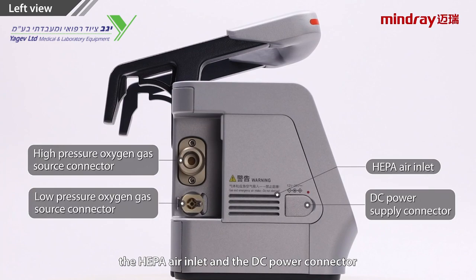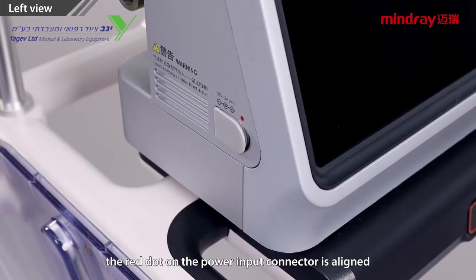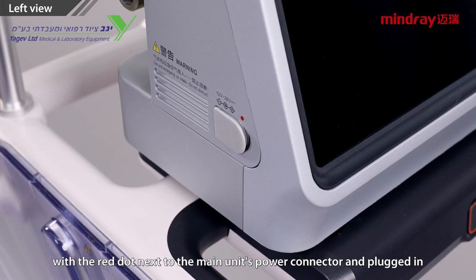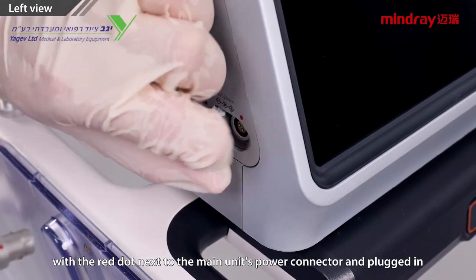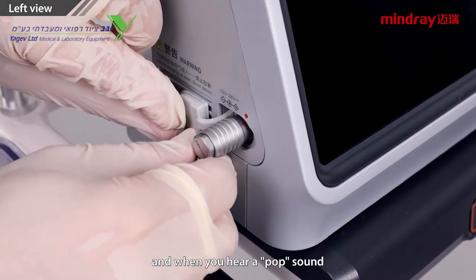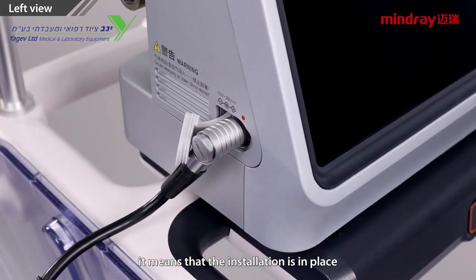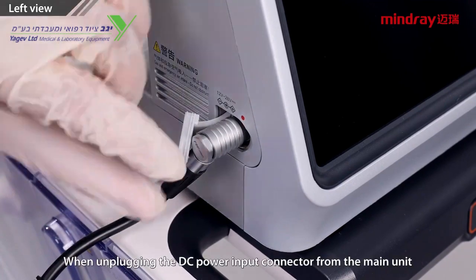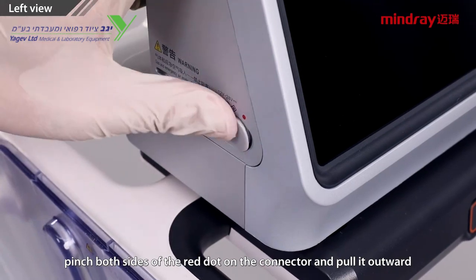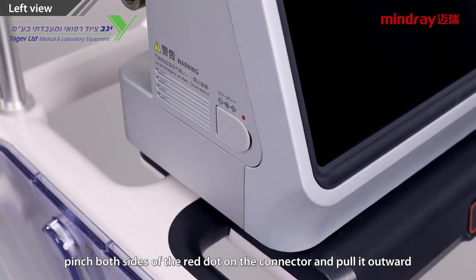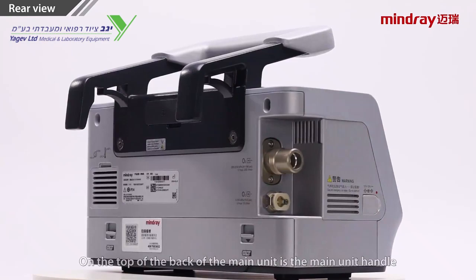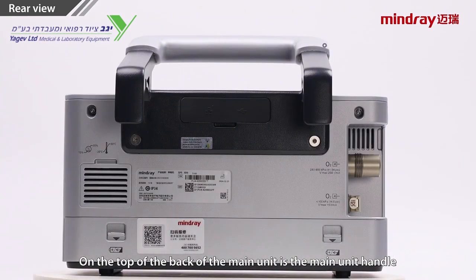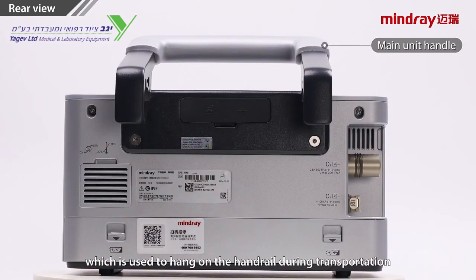DC power connector. When connecting, the red dot on the power input connector is aligned with the red dot next to the main unit's power connector and plugged in, and when you hear a pop sound, it means that the installation is in place. When unplugging the DC power input connector from the main unit, pinch both sides of the red dot on the connector and pull it outward. On the top of the back of the main unit is the main unit handle, which is used to hang on the handrail during transportation.